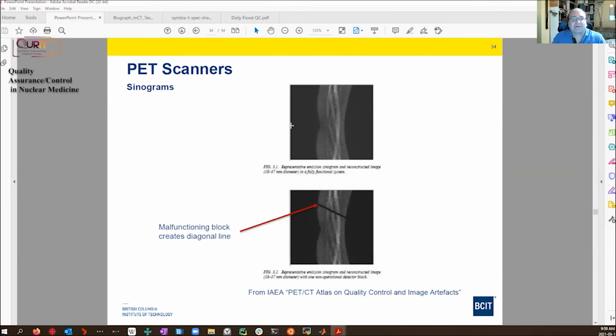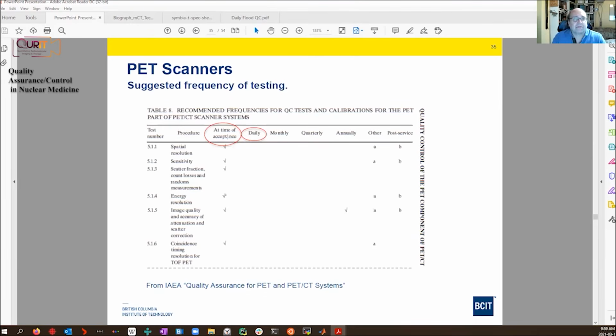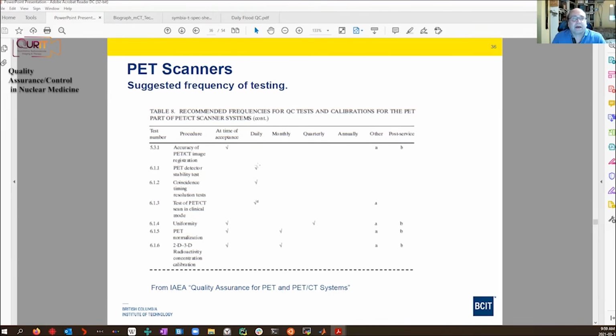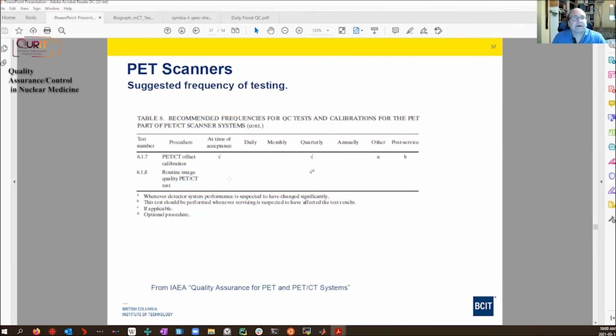So here's an example. This is a clinical sinogram, but if we see a diagonal line like this, that's a problem with the detector block, and that's going to cause problems in the reconstructed image. Again, these are done at different frequencies. Some of these are done for acceptance testing, some are done daily. These are the recommendations in this publication from IAEA. Again, I don't have time to go through these, but just be aware. So for example, coincidence timing is done daily. The accuracy of PET-CT registration is on acceptance.